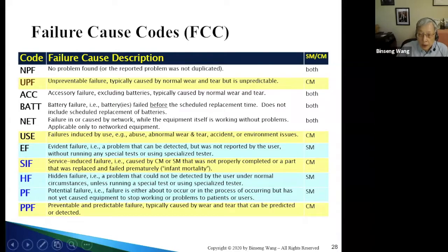Network failure. Nowadays, a lot of equipment is connected to the network. If there is a failure in connecting to the network, sometimes the equipment gives the impression that it's not working, but actually it's not the equipment, it's the network that failed. Use failure: failures induced by use. Abuse, abnormal wear and tear, accident, for example someone dropped an infusion pump on the floor. This is not necessarily the pump's problem. It's not a cause of a problem. It's just an accident. So that's not relevant here.